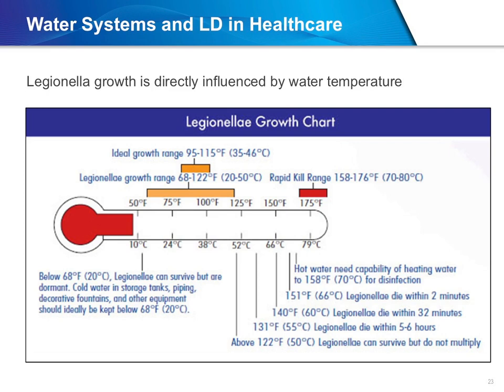The ideal range of temperature for such growth is 95 to 115 degrees Fahrenheit, but bacteria are known to grow and be active anywhere between 68 to 122 degrees Fahrenheit. Below 68 degrees, Legionella bacteria can survive but are dormant, while above 122 degrees, they can survive but do not multiply. The bacteria will die slowly when temperatures in the water reach 131 degrees Fahrenheit and die rapidly between 158 and 176 degrees.